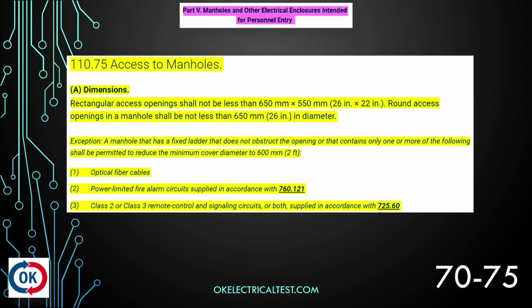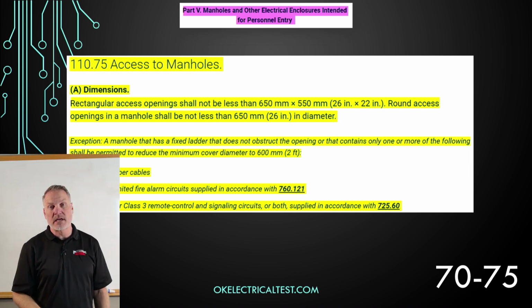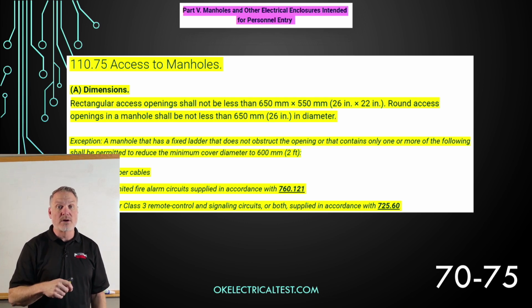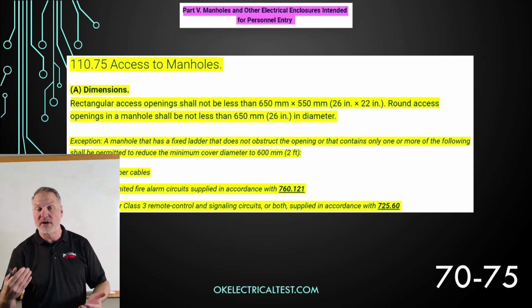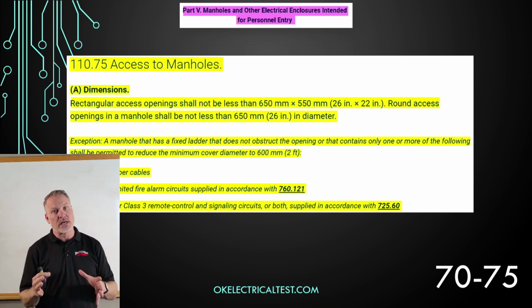That's going to be optical fiber cables, power limited fire alarm cables, or Class 2 or Class 3 remote control signaling circuits, or both, supplied in accordance with 725.60. And so if I've got a fixed ladder, it doesn't matter what kind of cables I have in there, I can reduce that down to 2 feet. If I've only got optical fiber cables down in there, no fixed ladder, I can still reduce it down to 2 feet. So the key word there is "or," right? If I've got a fixed ladder, or if I've got these cables, now I can reduce that down to 2 feet.